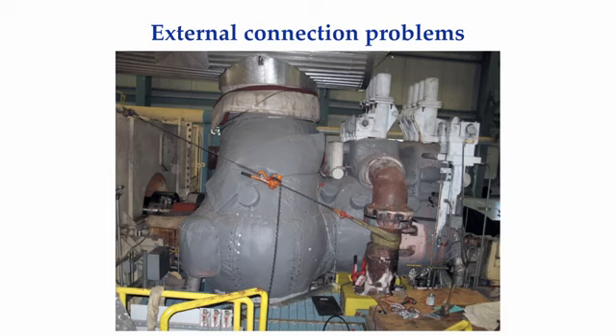If you ask the manufacturers of the machines, the flanges on our pumps and steam turbines are fluid connection points. They were never designed to be piping anchors. Our piping should be installed and supported so there is very little static or operating forces being induced into the machinery.